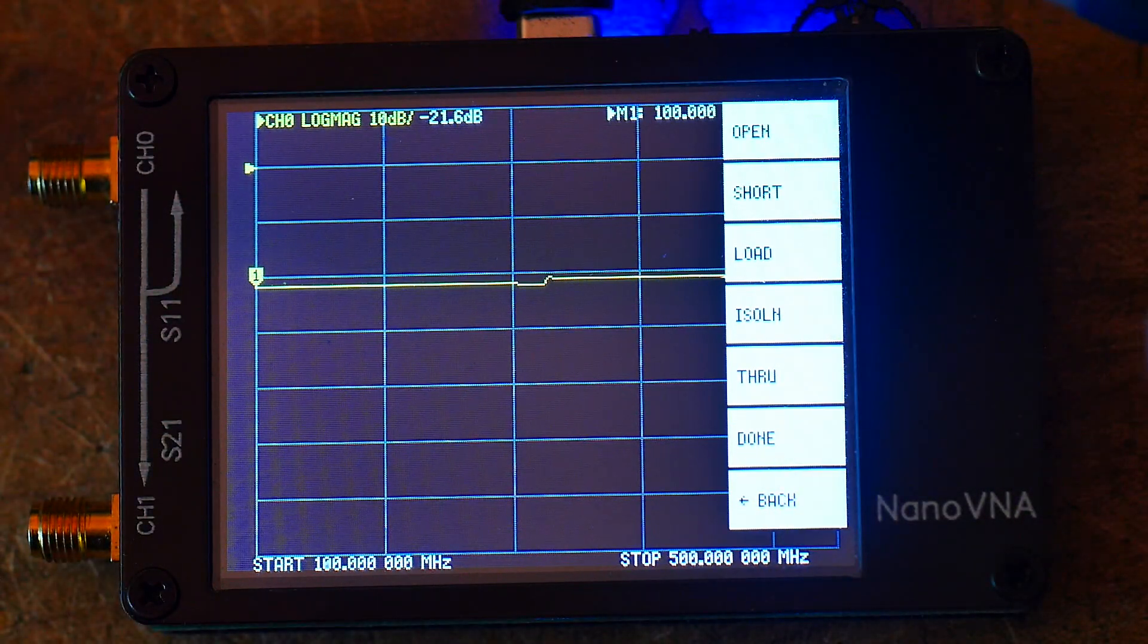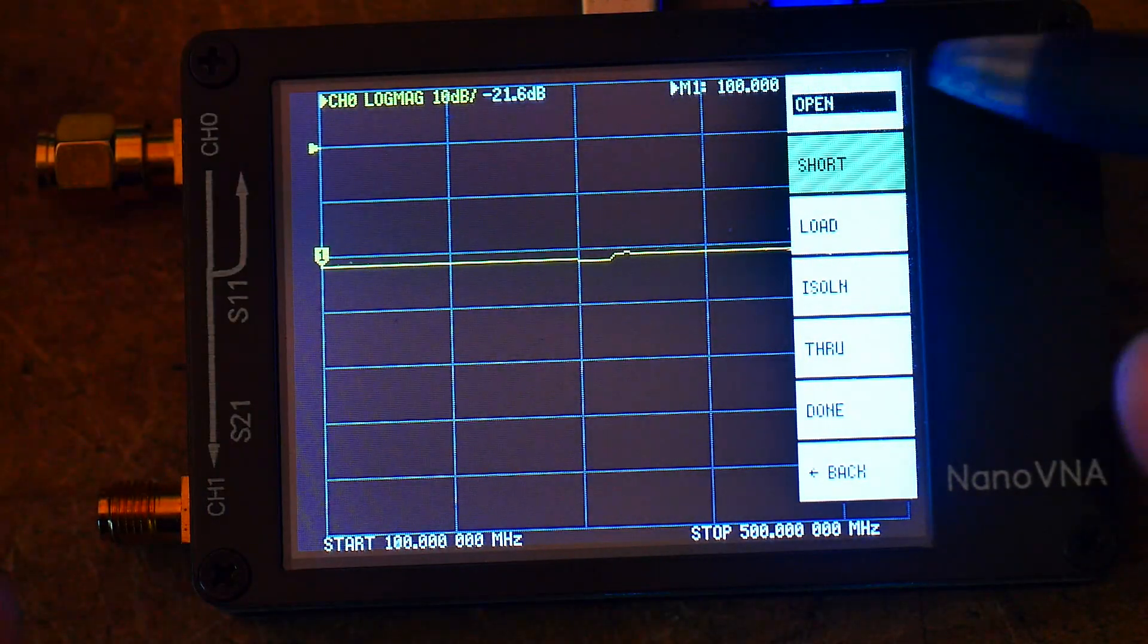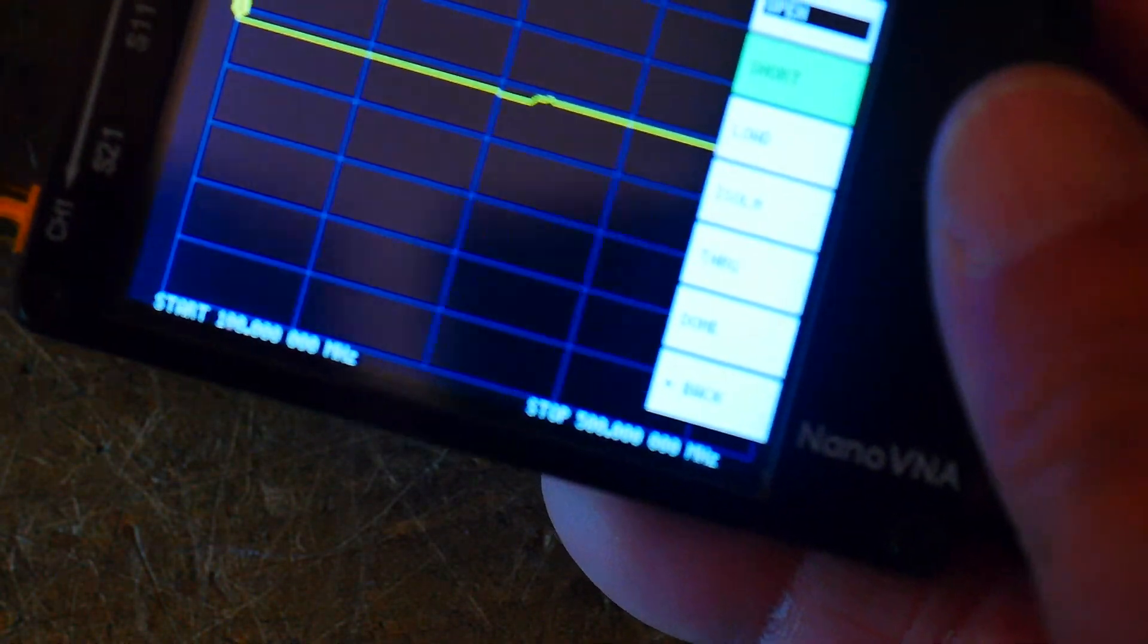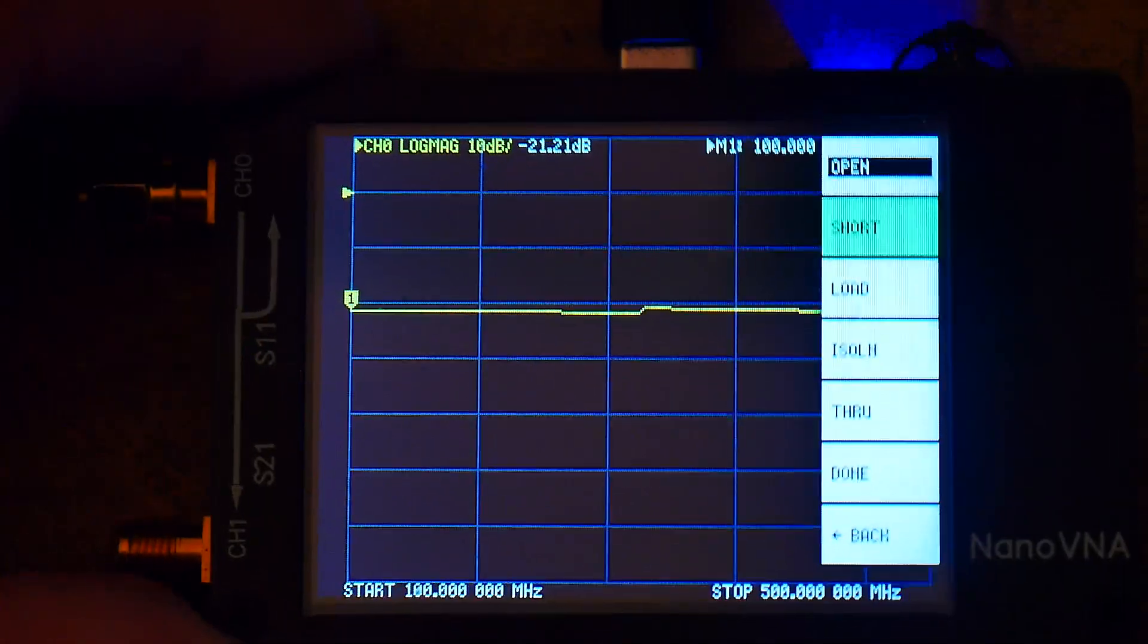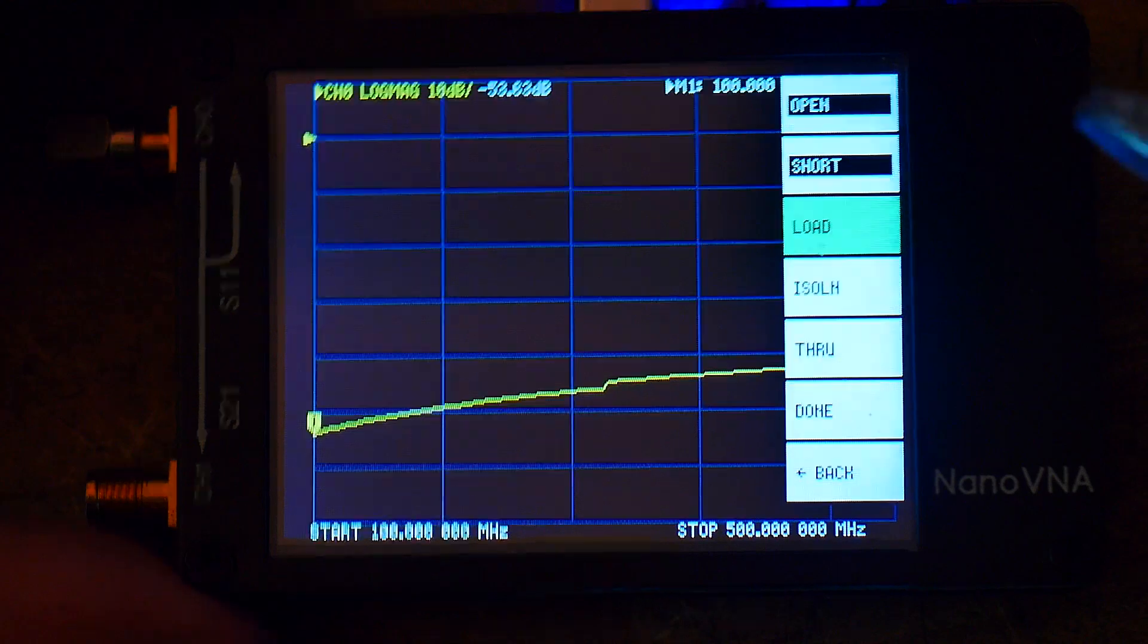So it says open. We're going to calibrate and open, which means we need to get our open. Remember, that's the one with the little O shape, the open one. So we're going to screw that on to channel zero. And when it's on, we're going to click on open. And that's it done. It's highlighted. It's done. Calibration is really fast. Next one is short. That's the shiny one. Put that one on. And we'll click on short. Done. Now we'll put in the load. And we'll click on load.